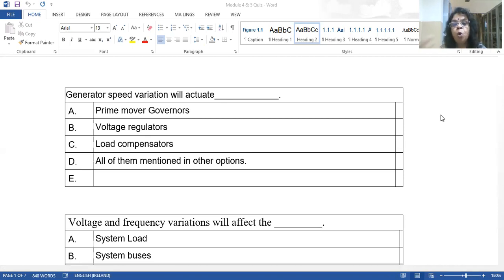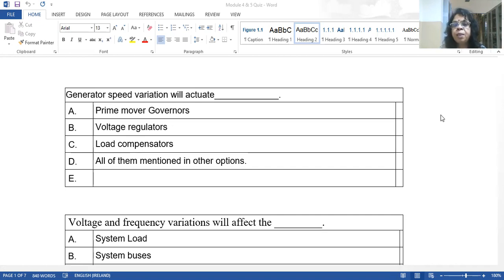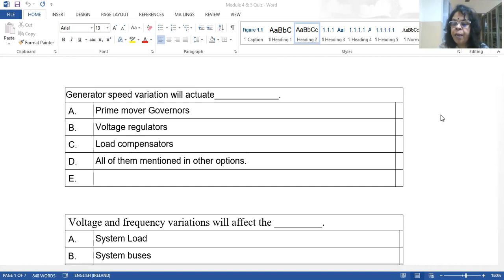If the frequency is more than nominal, it means demand is less than generation — the excess input energy goes into the kinetic energy of the rotor and speed increases. So whenever frequency increases, we must reduce the turbine output. Similarly, when load increases, frequency falls — a drop in frequency implies generation is less than demand. The kinetic energy is converted to electrical energy and the generator slows down, so turbine output must be increased.